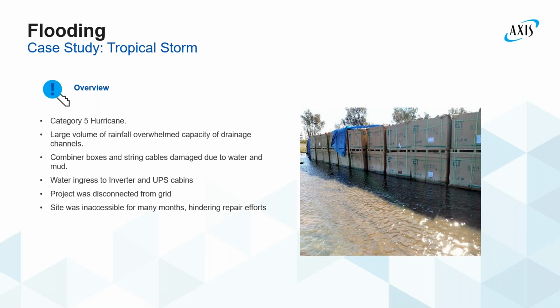A lot of water ingress to the inverter cabins and the UPS systems that were there already, and then critically, the project became disconnected from the grid. In Axis, we've seen this as a problem on other sites as well. If we're relying on the grid to provide auxiliary power when your wind farm or solar farm shuts down from the storm, if that power gets taken off because the national grid disconnects, then all the heating, cooling, and air conditioning fans in your inverter cabins stop working too.